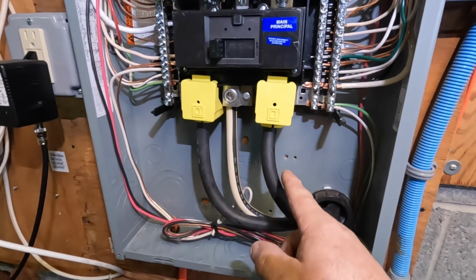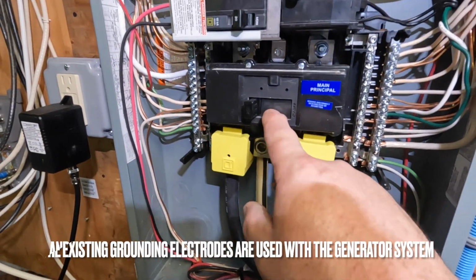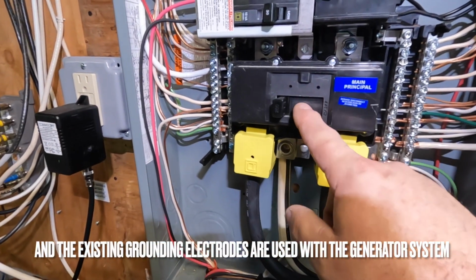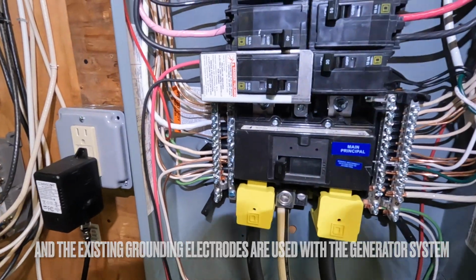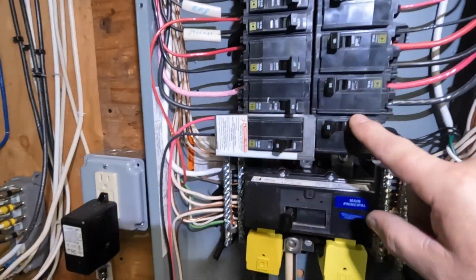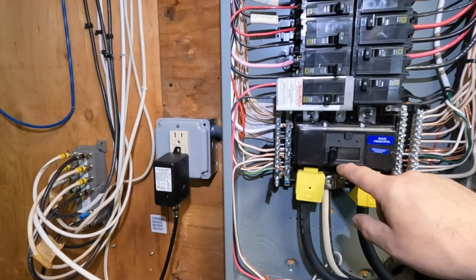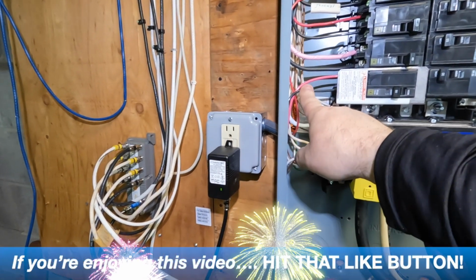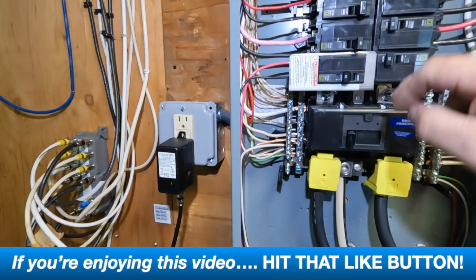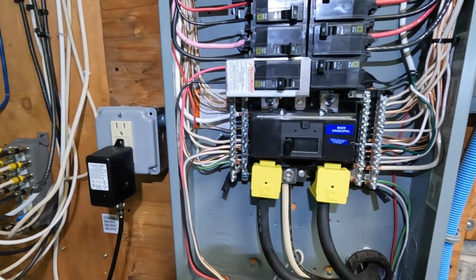Right now, the main utility supplies power to the main breaker, and the main breaker supplies power to the bus bar which the circuit breakers are attached to. All right. So in theory, what we're going to do is use this from our generator to supply the circuit breaker to supply power to the bus bar when the utility loses power.